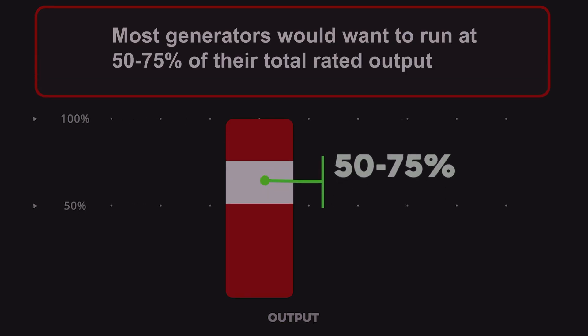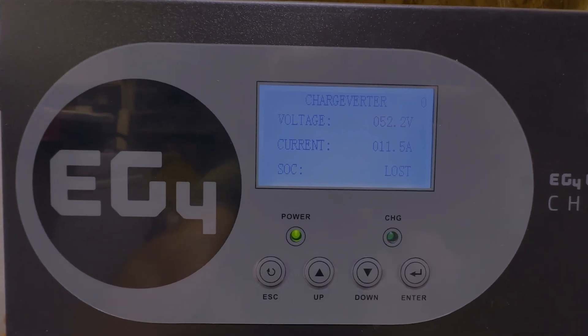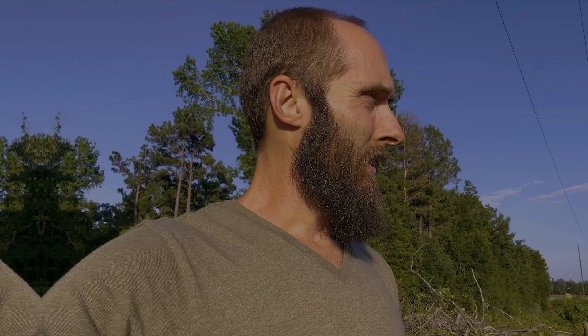I forgot how much I dislike generators — I love having it for backup and keeping everything online when I don't have enough solar generation, but they sure are noisy. One thing to keep in mind when sizing your generator: most generators are going to want to run between 50 and 75% of their total rated output. It doesn't mean you can't max it out, it just means it won't be as efficient and it'll produce dirtier energy going into your Chargeverter. For a 6,500-watt generator, I want to keep it around 4,500 watts to efficiently use the fuel without over-burdening it — and 100 amps at 48 volts is kind of the upper end of that range.